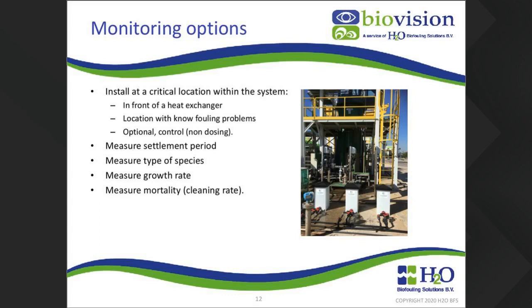This monitor, as mentioned, measures the settlement period, the type of the fouling, and the rate. In addition, you can measure the mortality rate. So when you have a foul system and the plates or the coupons are fouled with organisms, you adjust your dosing regime, and you can see the effect also on the coupons of the monitor.